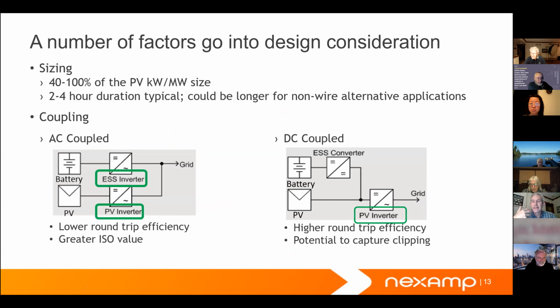So when we design these solar plus storage facilities, and we can have a storage-only facility too, but when we put it with a renewable facility, we typically size it to be about 40% to, in some cases, 100% of the solar size. So if the solar project is 10 megawatts, we would size the storage anywhere from 4 megawatts to 10 megawatts, depending on where we are in the usage.